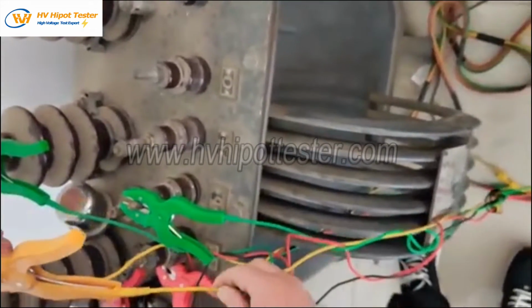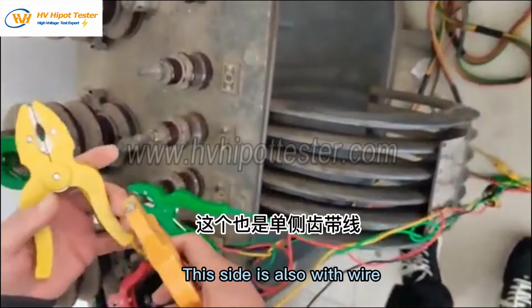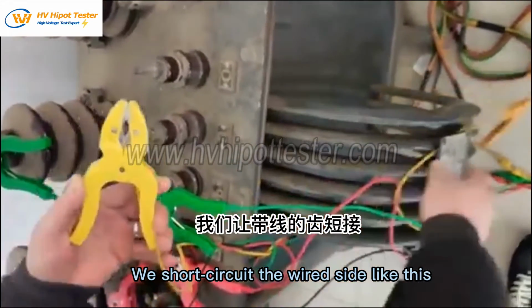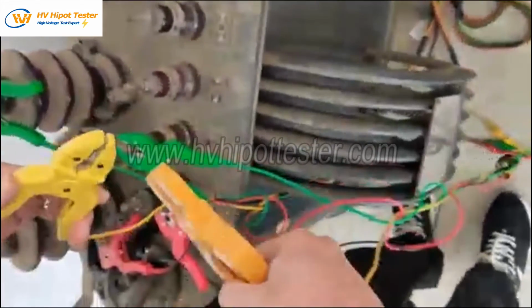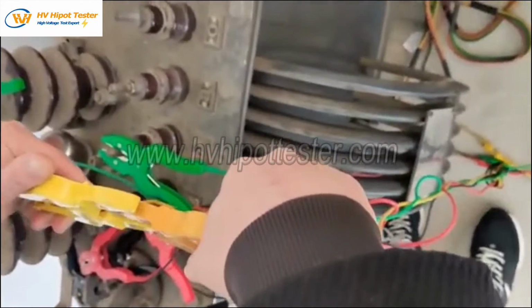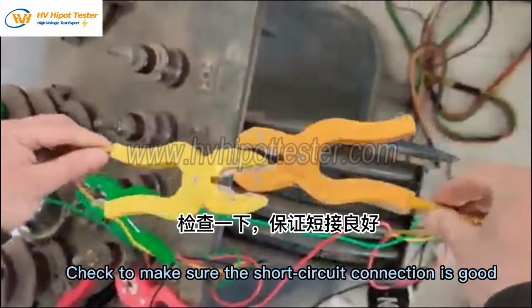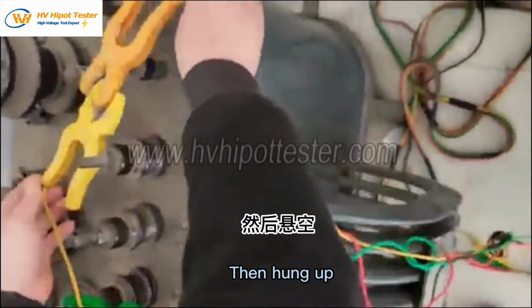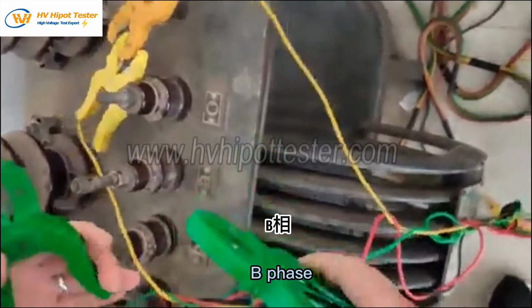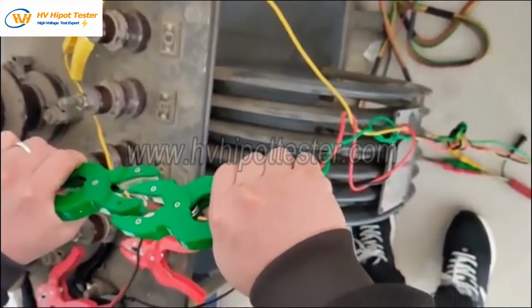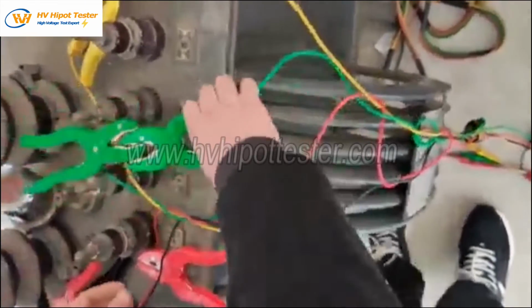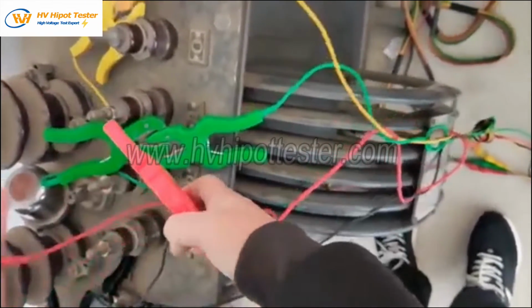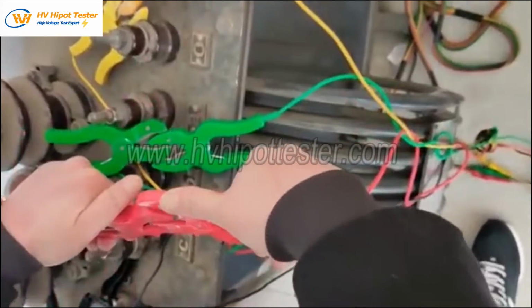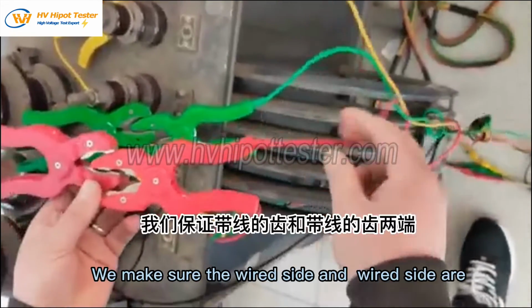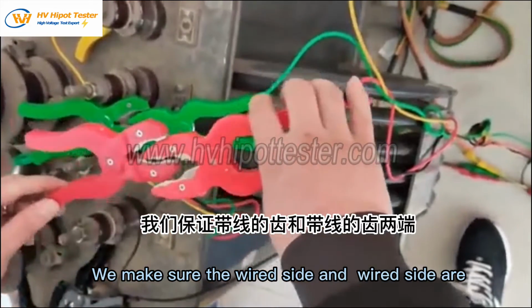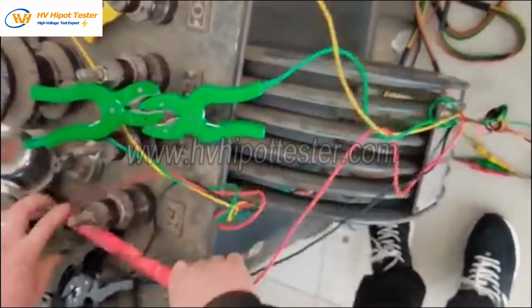Watch carefully. This side is with wire. This side is also with wire. We short-circuit the wired side like this. Check to make sure the short-circuit connection is good, then hang up. B phase. Short-circuit connection, hung up. Phase C. We make sure the wired side and wired side are short-circuit connected well.